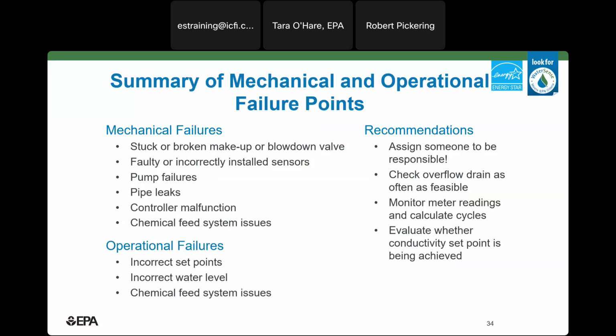So I just covered a ton of information and best practices in a short amount of time. I wanted to take a minute and summarize some of the common failure points that could lead to water waste or cooling tower damage. As far as mechanical issues, you can have a stuck makeup or blowdown valve. A makeup valve that is stuck open will continually fill and overflow the tower. A blowdown valve that is stuck open will continually drain water, essentially creating a single pass system that also wastes cooling tower chemicals. A blowdown valve that is stuck closed will not be able to remove minerals from the system at all and could eventually lead to a scale event.